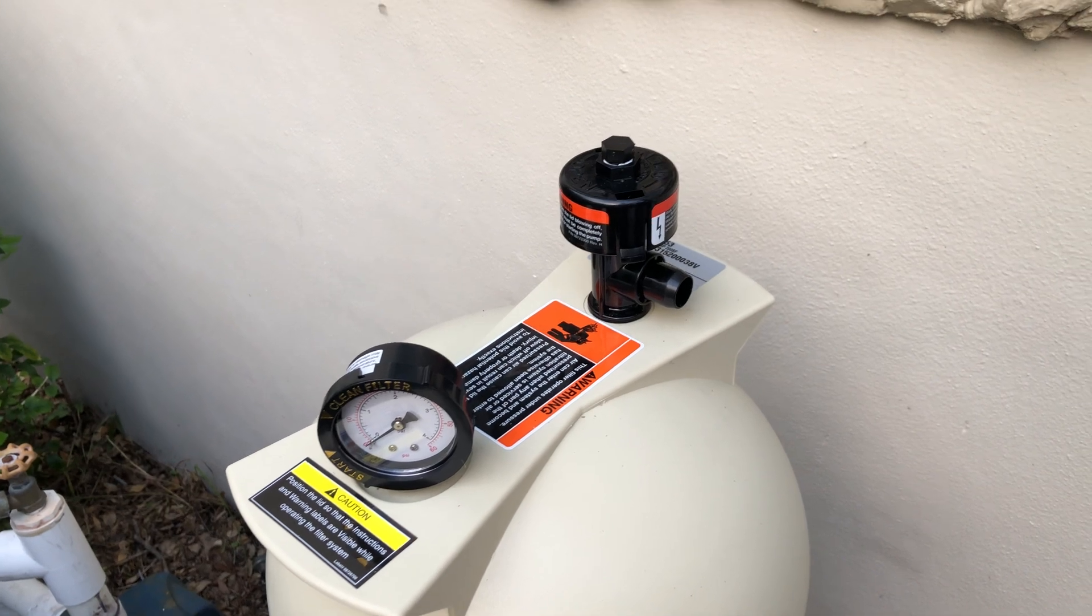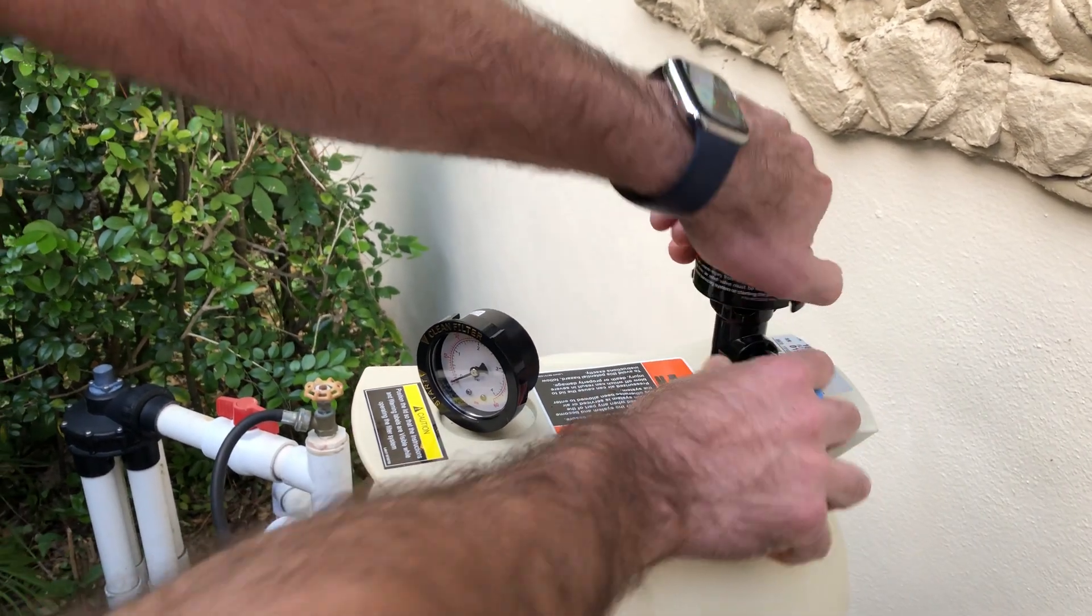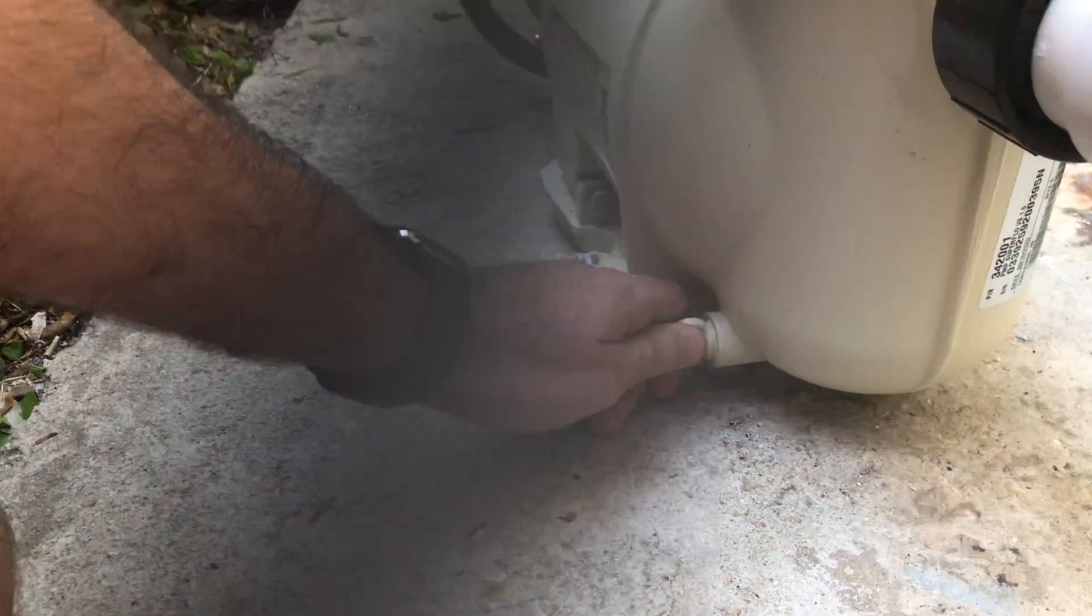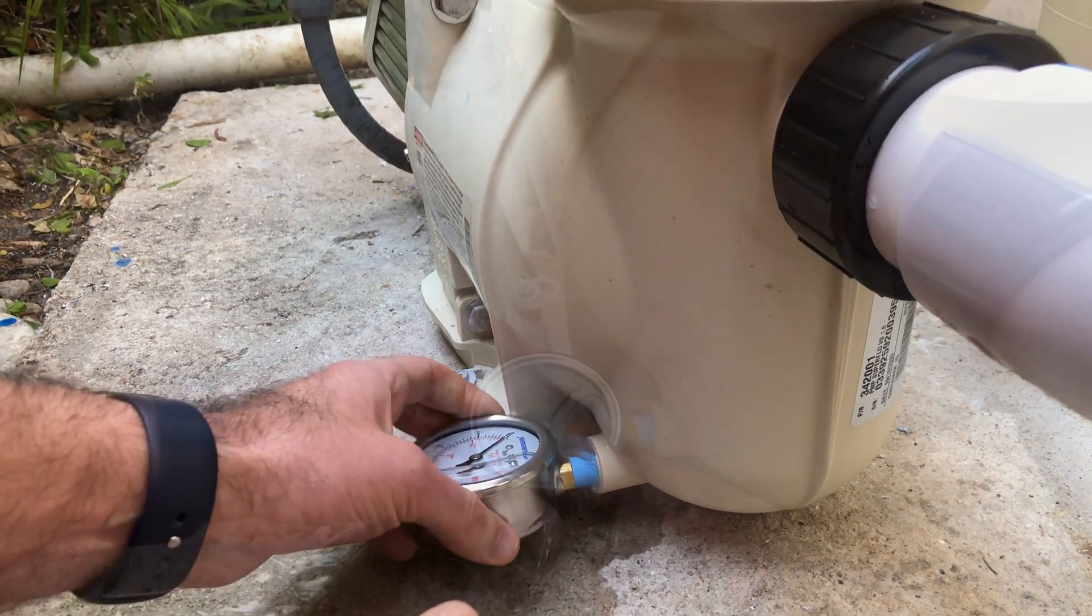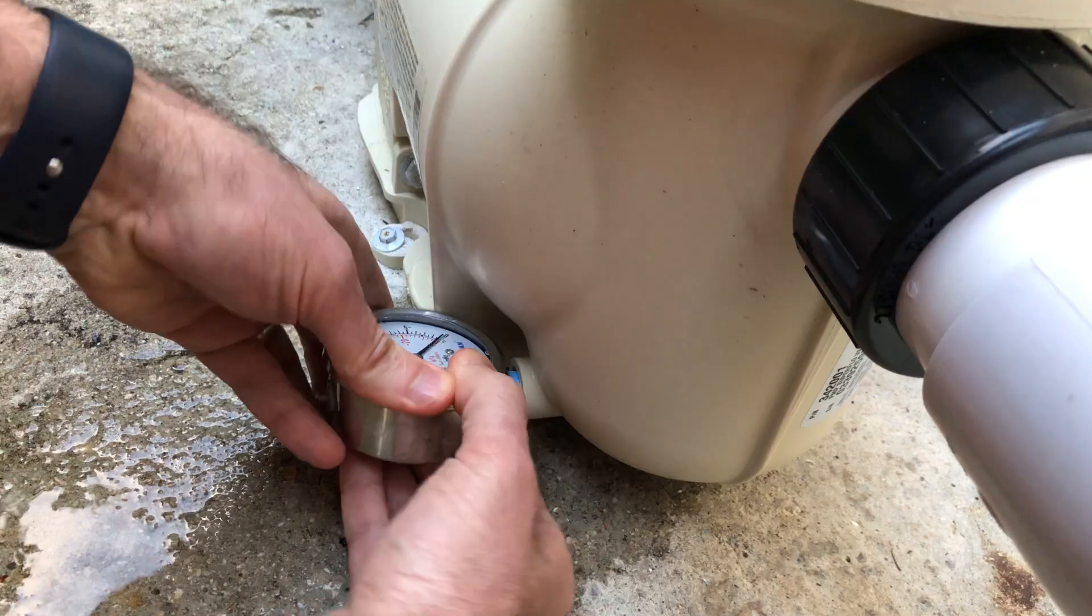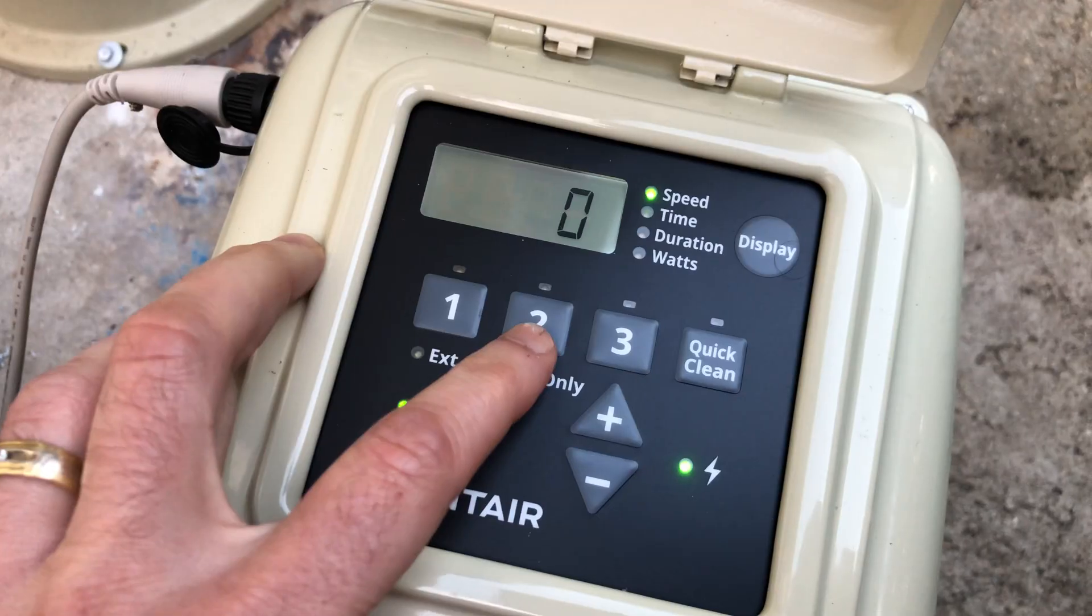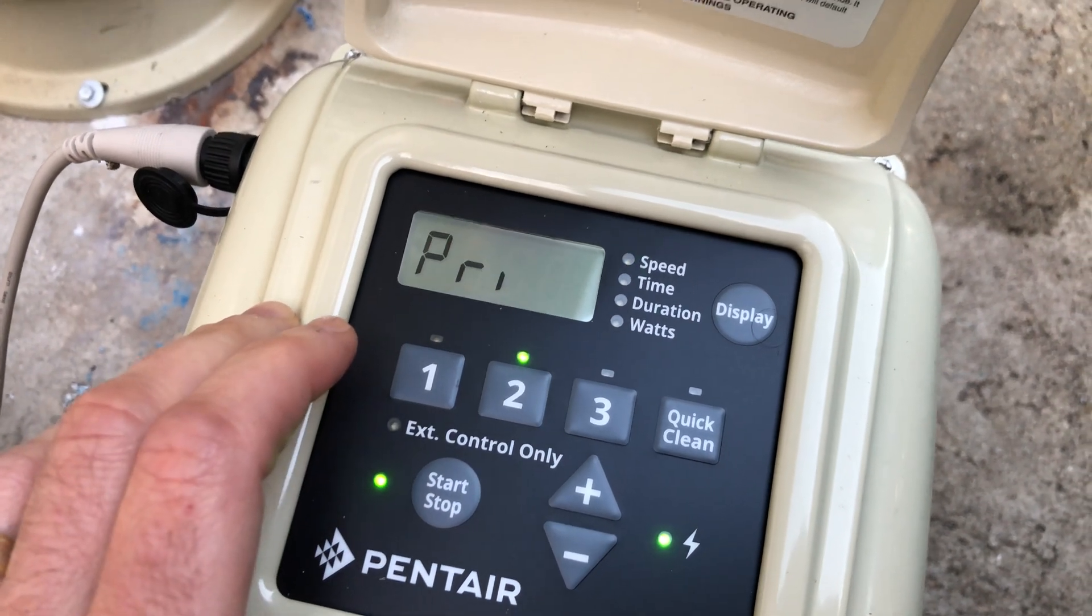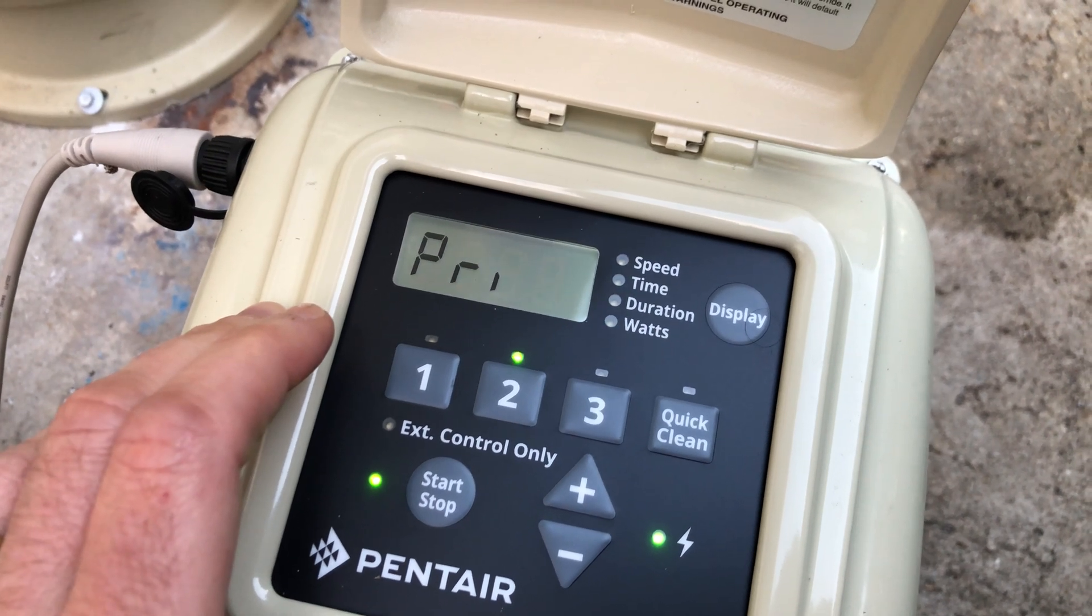So let's go ahead and get started by relieving the pressure in the system. Now I'm just going to go ahead and unscrew this drain cap. Alright, so now here at the pump I'm going to set it to speed 2. So it's going to start priming, and then it should go into 3,000 RPM once it's done, and I'll check my readings after that.